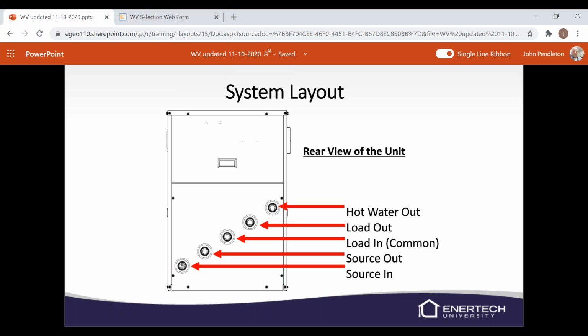You're also going to have strainers on your source in and your load in connections that come with the unit. Again, anytime we have braze plates, the braze plate manufacturer requires us to use a strainer. Those passageways through those braze plates are pretty small, so we want to make sure that we're capturing any kind of debris that could be in the system or out in your piping.